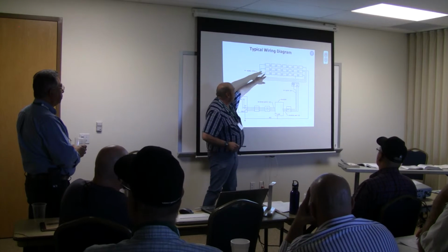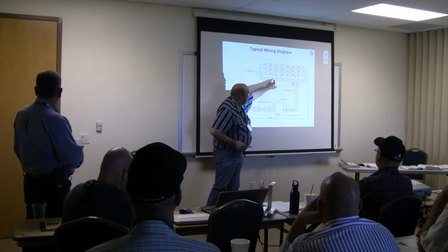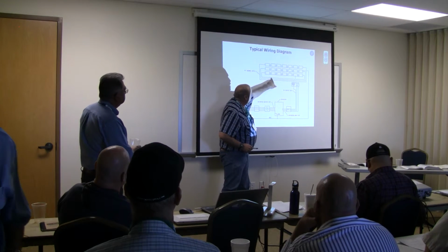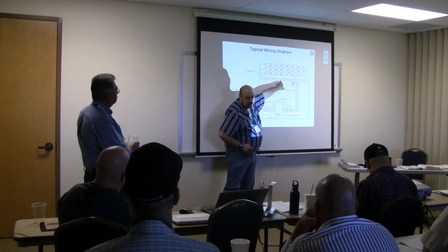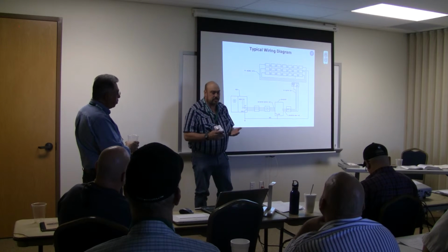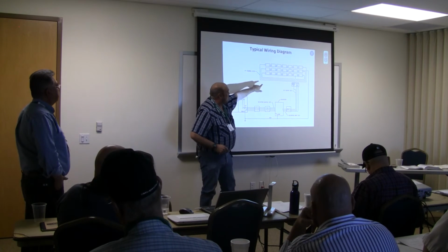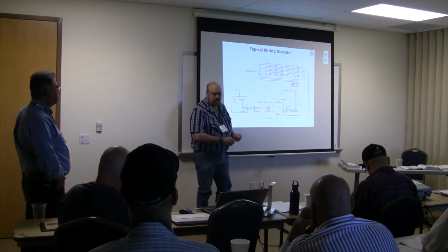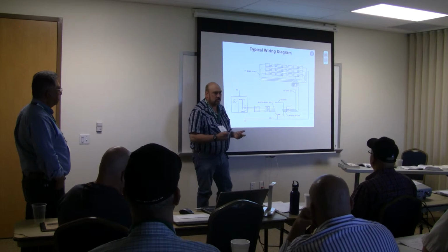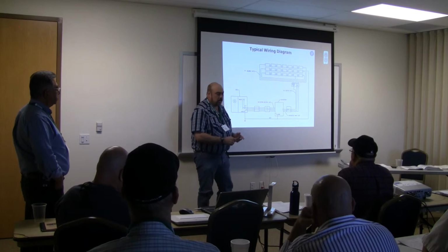So then you're going to see, probably out of these, some free air type PV wire. This looks like it's a combiner box here, but typically they'll have a junction box on the roof, and then they'll switch over to EMT. Okay, that's where you're going to start sizing for the number of conductors, depending on how many strings they've got here that are going to come into that conduit. So in Article 310, there's a number of tables for your ambient temperature reductions.